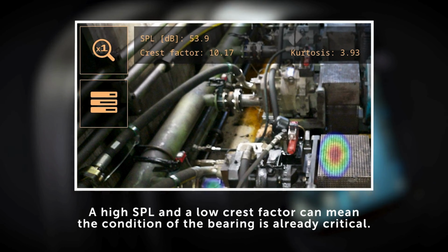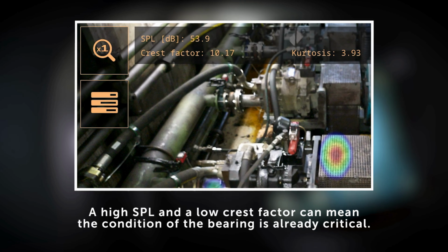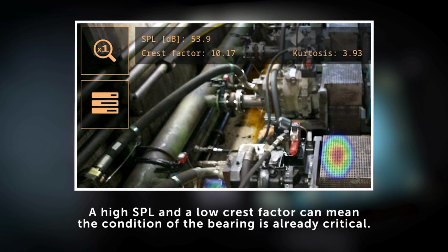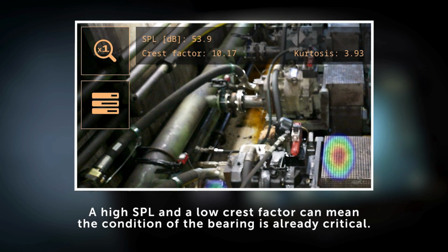This means that if a bearing shows a very high SPL compared to healthy bearings, but the crest factor is relatively low, the condition of the bearing might already be critical.